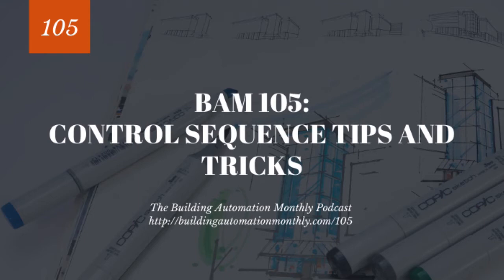Actuators, relays, interface cards, those are all outputs. And so that's what you want to look at. That's your first thing, inputs and outputs. Then once you've done that, you can look at how the system is being controlled. And this is kind of a rule of thumb that I've used. Once again, I said this isn't going to be specific to any single situation, but use this as your guide.